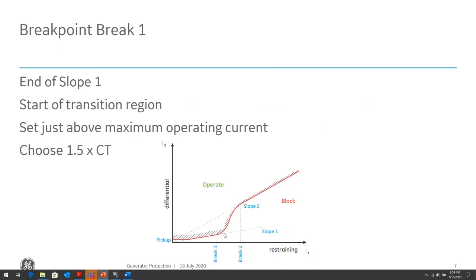So then the transition from slope 1 to slope 2 should be set above the maximum operating current, or your full load current. A good margin is about 1.5 times your full load current. And if you've sized your CT properly per your full load current, it should be about 1.5 times your CT rating.